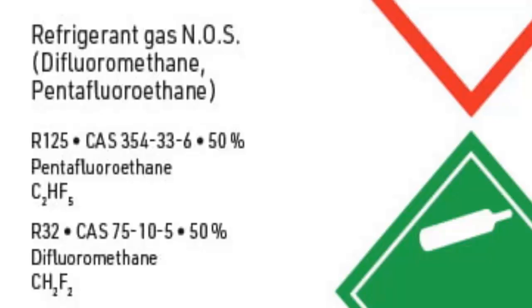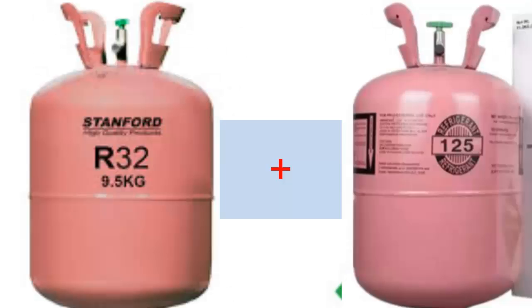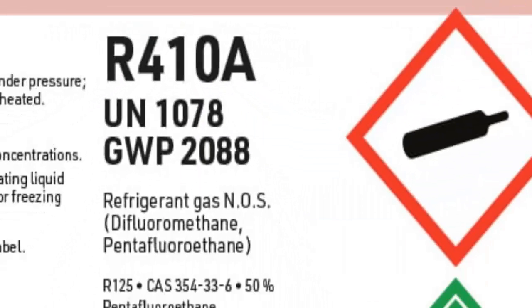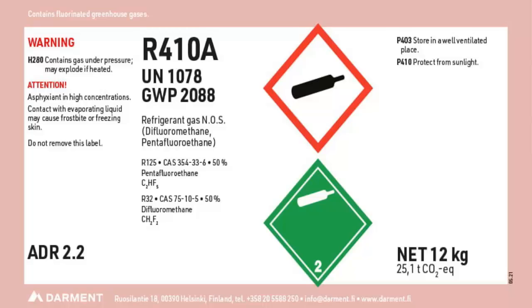The fact of having R125 presents a problem: it is the global warming potential — the high global warming potential. All gases that have R125 will tend to have a high GWP. In this case for R410A it is 2088. The R32 lowers the value a little, but having R125 already puts it above 1500, which is the threshold of many environmental limitations — it is above that with a value of 2088.